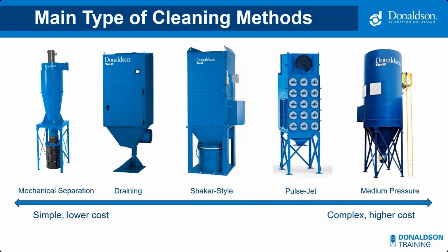Similarly, dust collectors can range from very simple, using a cyclone that uses mechanical separation to separate dust from an airstream, up to a much more complex medium pressure cleaning system. Typically for these, we're talking large baghouses that would use a separate positive displacement pump to generate compressed air and pulse clean the filters. There's a variety in between that we'll cover today.